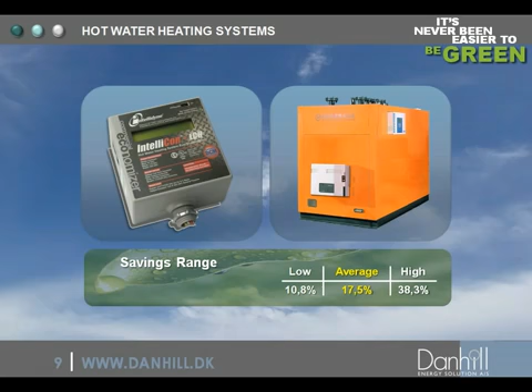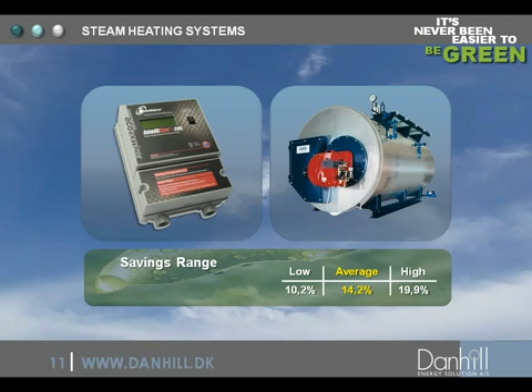In Denmark, test results have been confirmed by Trefor, a multi-energy company providing electricity, drinking water and district heating to large parts of Denmark. Trefor measures 30% savings at a Danish client. The fuel-saving economizer for commercial steam heating systems saves energy by adjusting the burner run pattern to match the system's heat load, determined by using a pressure sensor that monitors the boiler's steam pressure and the rate that the pressure changes.